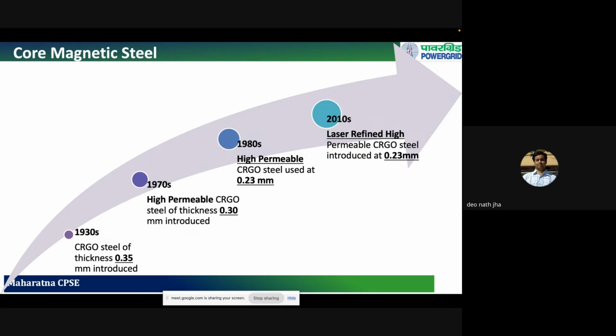What this has done is, the lesser the thickness of the steel laminations, the more evenly distributed the voltages across the transformer core. And this laser refinement has led to a reduction in manufacturing malpractices and unevenness of those laminations. So it has led to better transformation capacity and lower failures in transformers.